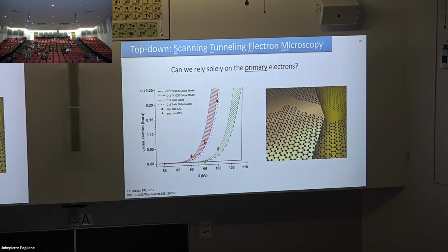This data is for graphene. This is for graphene, yeah. These two graphs are different isotopes of carbon. If you do other 2D materials, like the TMDs in particular, they are much more susceptible to radiation damage. You get a higher yield of sputtering, which is why I think people use something like 80 kV or lower for imaging TMDs, if you don't want defects induced by you looking at it.